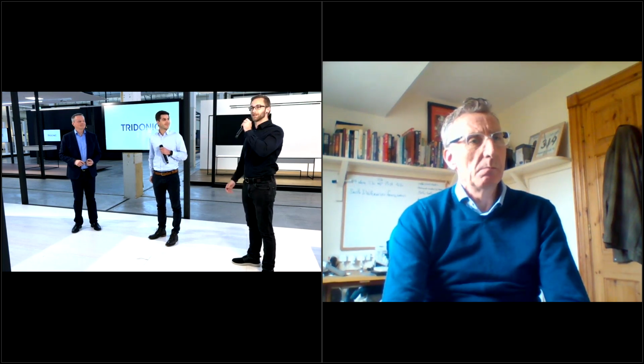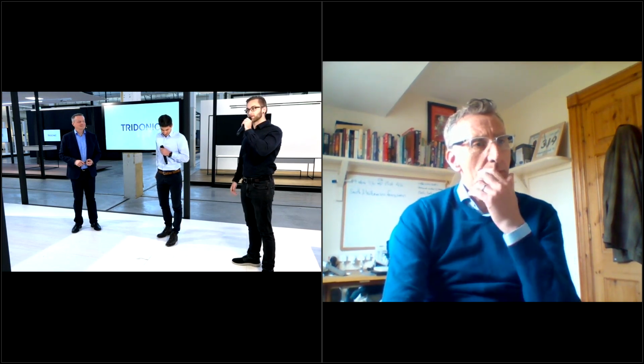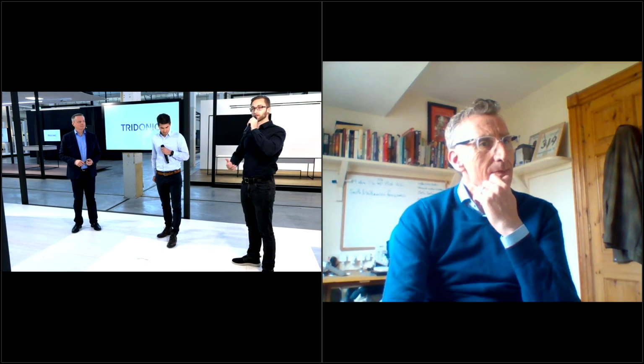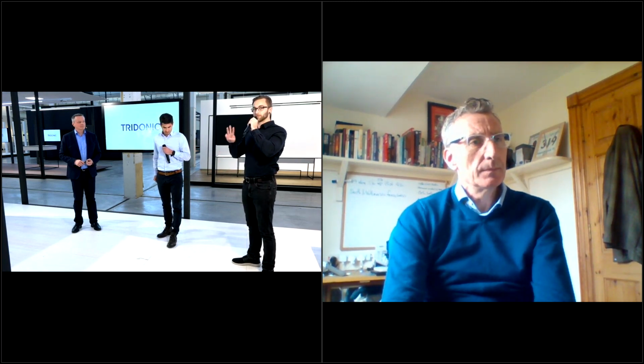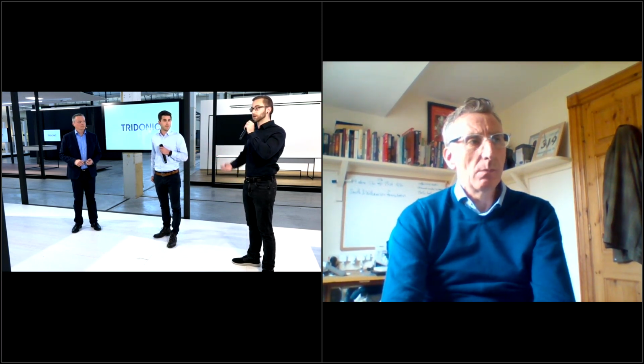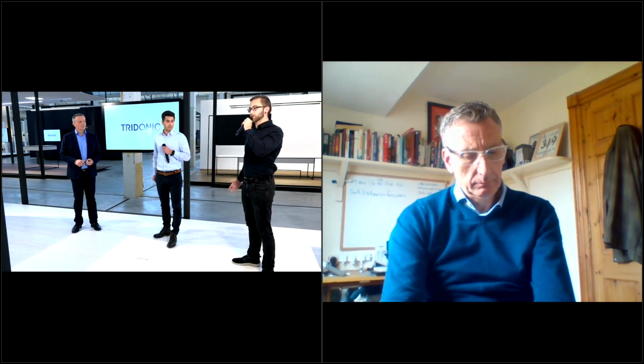Thanks for the question. The system itself works so that one SceneCom controller can control 3 DALI lines, meaning 64 devices per DALI line. The same is true even in the wireless world: if you connect a wireless gateway to a DALI line, you can still connect 64 luminaires to it. That gives you in total 192 luminaires per SceneCom controller.